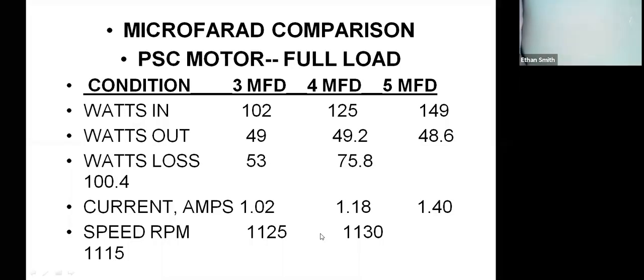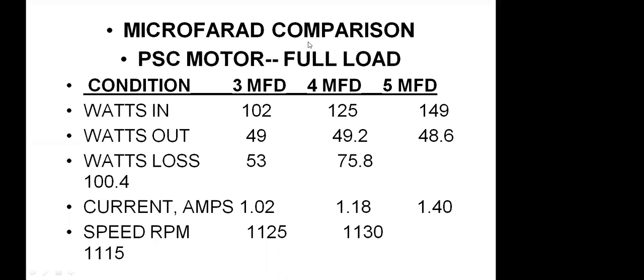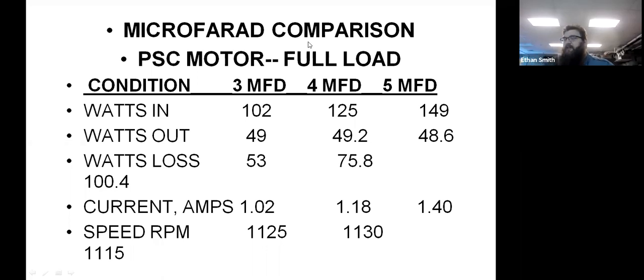Outside of that, we go back to the problem where we are talking about motor inefficiency loss, and we're just causing extra heat. So what does extra heat do to motor windings, guys? Cause them to smoke. Yep, you're going to have premature motor failure. Higher amps. Higher amperage, all the bad things. So we don't have to miswire the motor in order to get the nothing good happening. There it is, right there. We can simply not do our maintenance, not check the capacitors, and we'll end up in that nothing good category eventually. So this is one thing that gets overlooked a lot when we're dealing with electricity and motors: people just don't check the capacitors.